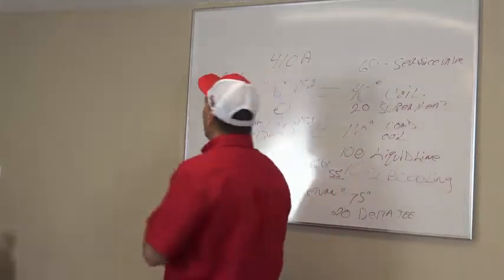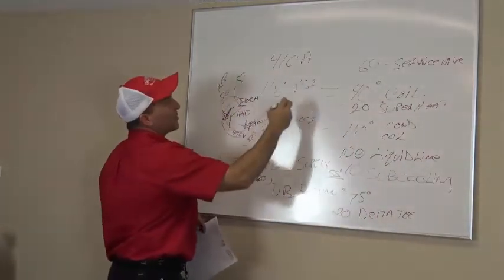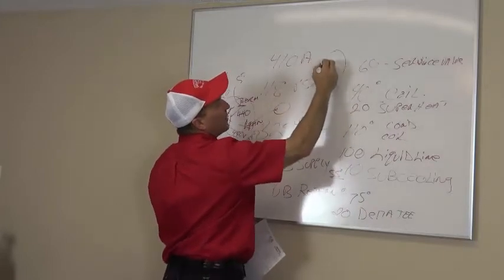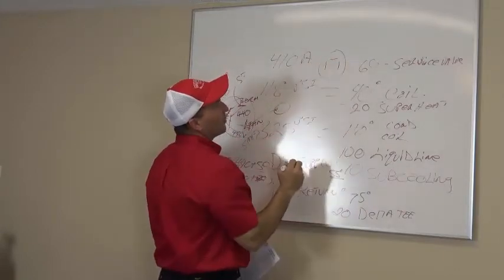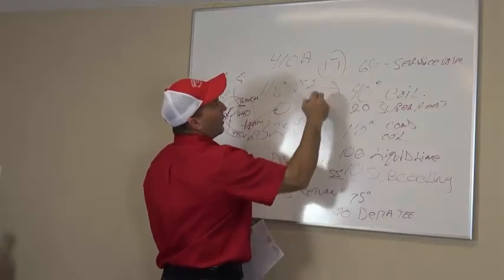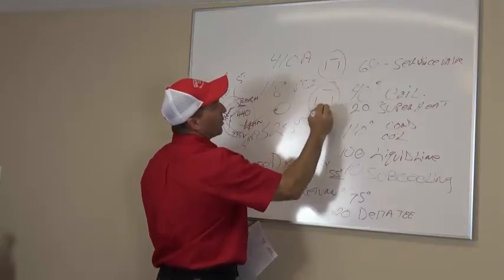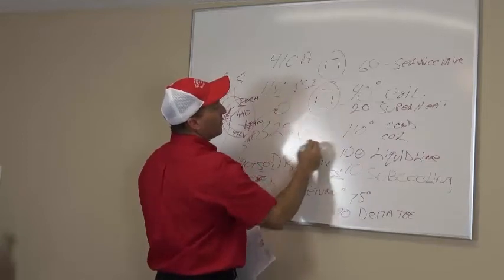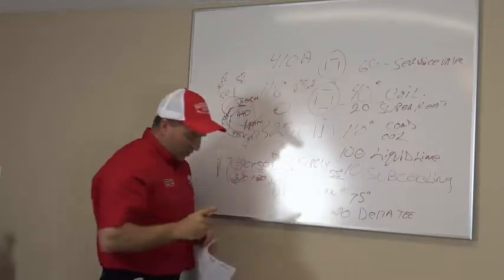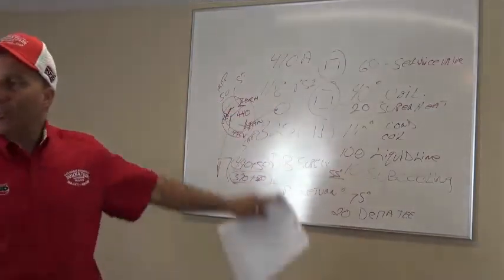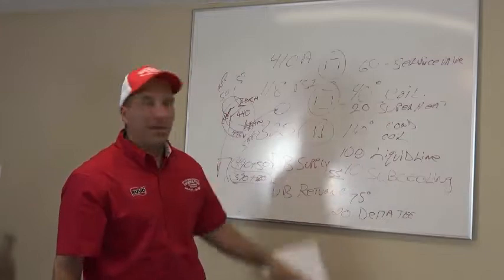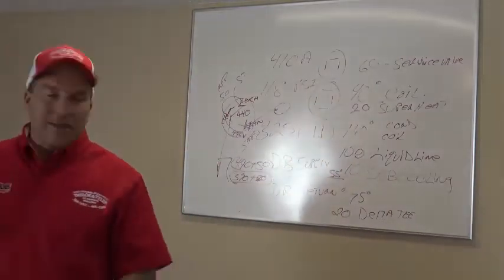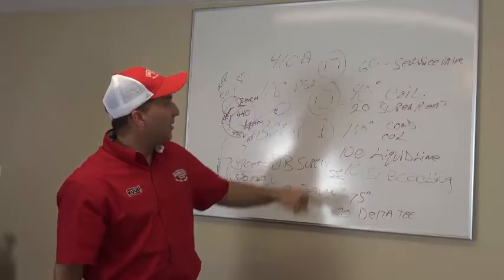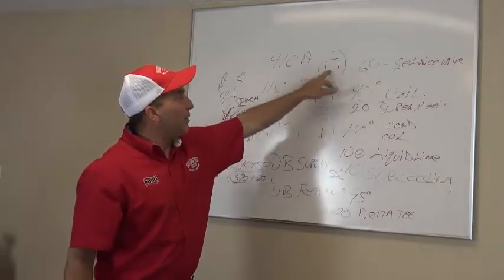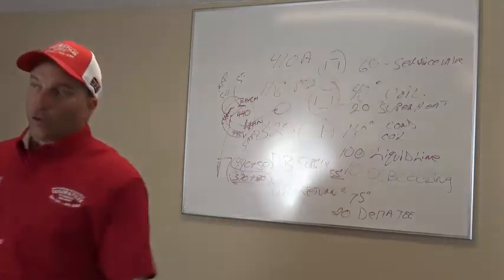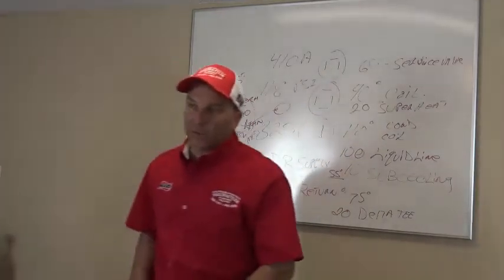And here's something else that you can determine which one of these is which. On your hermetic, you're going to have 3 terminals on it. On your common, you're going to have 4 terminals on it. And on your fan, you're going to have maybe 1 or maybe 2 terminals on it. That's how you can actually look at the capacitor and tell which one's common, hermetic, and fan. Most of the time, it's just 1 on your fan. So it's usually 4 on your common, 3 on your hermetic, and 1 on your fan is what it normally is. Okay, but sometimes they got 2 on the fan.